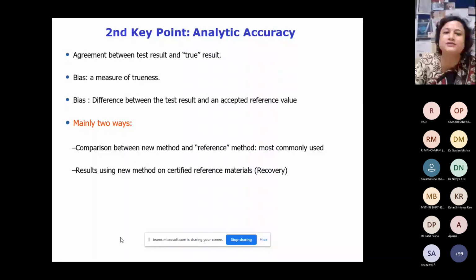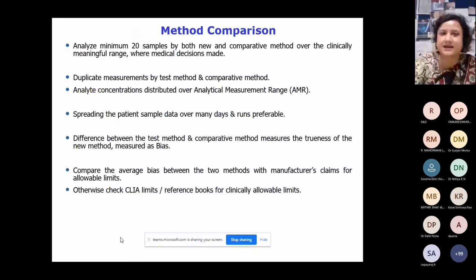So we take the reference method. Suppose you have a new instrument and you have been using another instrument for a long time, or there is a gold standard method; you can do the accuracy check with that. For that, analyze a minimum of 20 samples by both the new method and the comparative method over the clinically meaningful range where medical decisions are made. Take duplicate measurements by the test method and comparative methods. Analyte concentration should be distributed across the analytical measurement range, and spreading the patient sample data over many days and runs is preferable. The difference between the test method and comparative method measures the trueness of the new method.